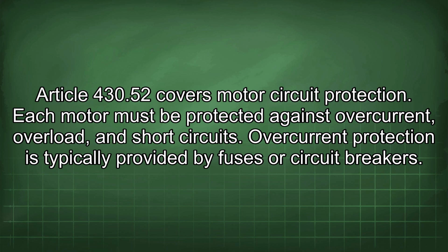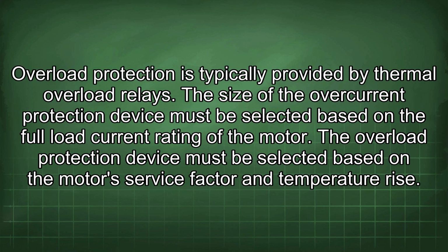Article 430.52 covers motor circuit protection. Each motor must be protected against overcurrent, overload, and short circuits. Overcurrent protection is typically provided by fuses or circuit breakers. Overload protection is typically provided by thermal overload relays. The size of the overcurrent protection device must be selected based on the full load current rating of the motor. The overload protection device must be selected based on the motor's service factor and temperature rise.